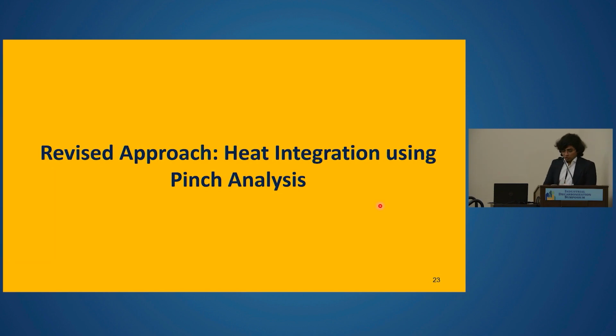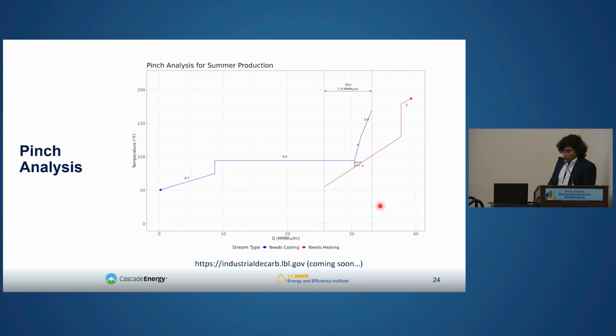So our revised approach, much as described by Raj earlier, is using pinch analysis to come up with a total heat integration for the site, and not directly go to the heat pump solution. When we did the pinch analysis for this facility, this is just showing one of the scenarios, a typical summer production day. And we found that we could use heat exchange to get to a water temperature of around 100 degrees. And then we only need the heat pump to get that final 30 degrees of heat. But this just shows one of the many conditions that can happen at the plant.